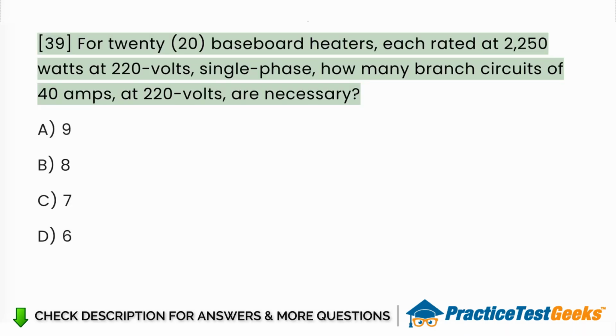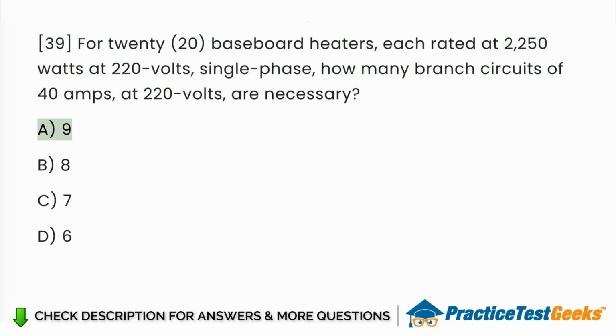For 20 baseboard heaters, each rated at 2,250 watts at 220 volts, single phase, how many branch circuits of 40 amps, at 220 volts, are necessary? A. 9. B. 8. C. 7. D. 6.